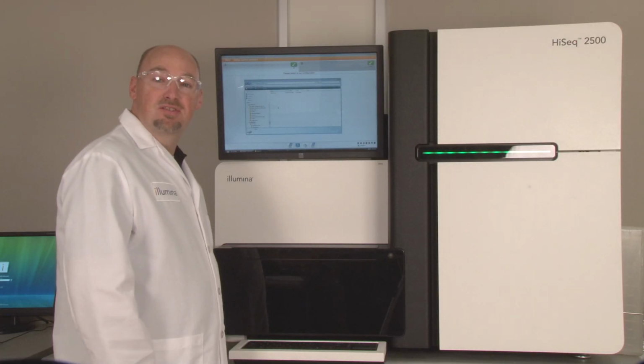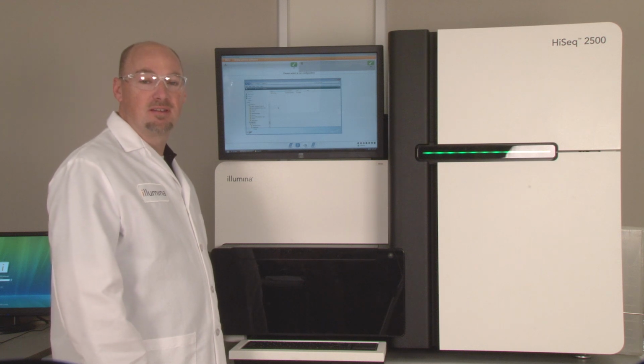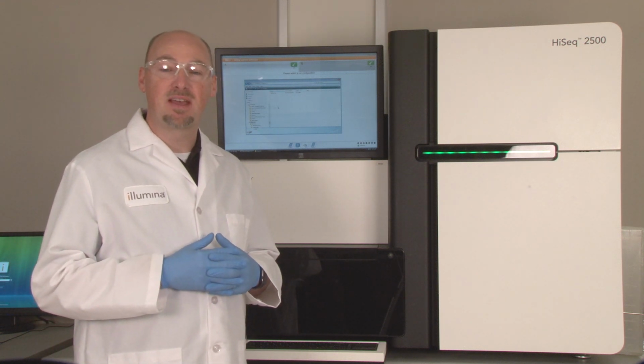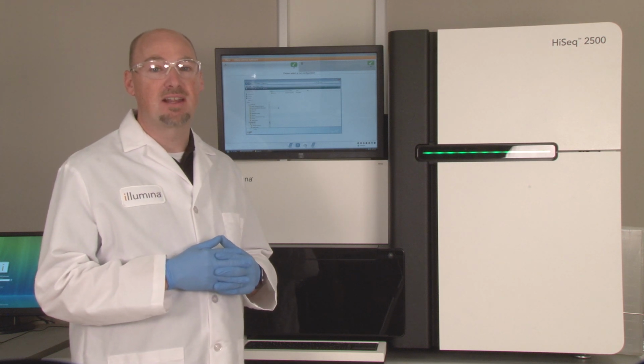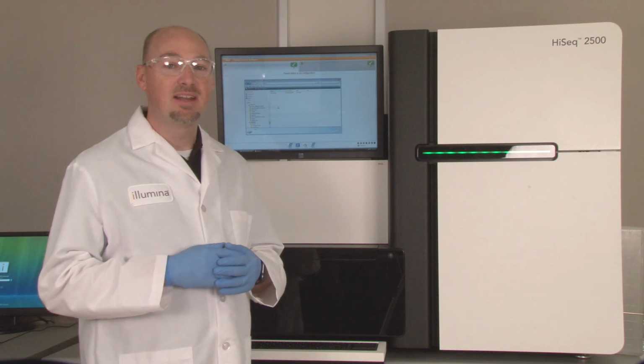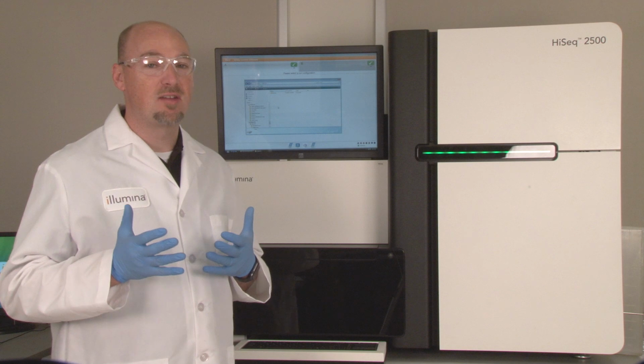If disk space drops below the safe threshold during the run, the software may pause the run and place the flow cell in a safe state. After disk space is made available, the run resumes automatically. However, this increases the overall run time, leading to inconvenience and delays, so it's best to format the appropriate drive before each run.